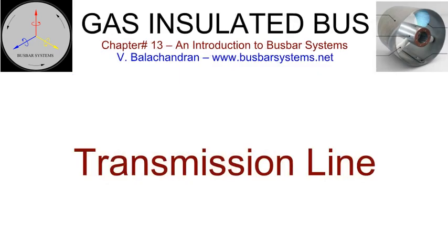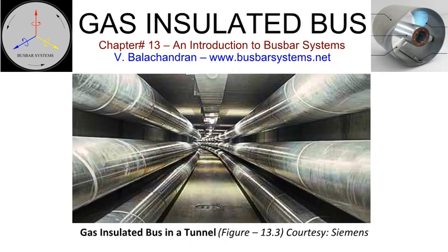Transmission line. Gas-insulated bus can be run in any of the following modes. Above ground. Gas-insulated bus can be run above ground, at a convenient height, supported on the structure. This mode is preferred when transmitting large power over long distances. In tunnels and trenches. Gas-insulated bus can be run below the ground in prefabricated tunnels and trenches. It is also run in trenches when there are road crossings.